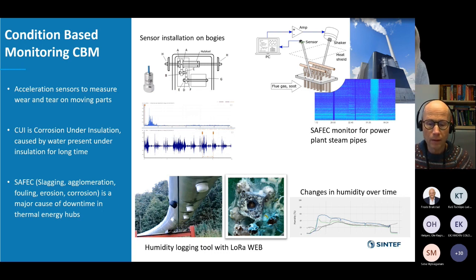Condition-based monitoring can also involve humidity-based sensing, a quite demanding environment for a sensor. This relates to corrosion under insulation: insulation can have little bits of water residue, and while you shouldn't have oxygen to cause corrosion, bacterial growth from water can create oxygen and cause corrosion. Getting the sensor inside without damaging it—since humidity is bad for a sensor—made the packaging, logging, and distribution really important. You need sensors in several places, so building something repeatable that can be installed in multiple locations to cover the area is very important.